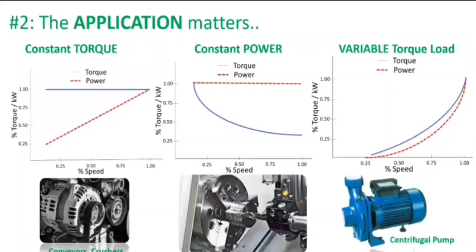So how we control the motor is really important. There are a lot of technologies available in the market. The standard one is you opt for a typical type coordinated system for a typical DOL or star delta method. DOL and star delta are the types of starting methods for a motor. Then we have soft starters, we have VFDs. The architecture also gets important, whether you're using a three product solution. By three product I mean a short circuit device, a contactor, and an overload relay, or an MPCB and a contactor. Or from Schneider we also have a unique single product solution.